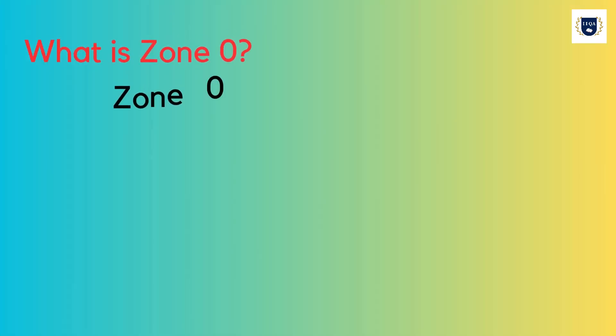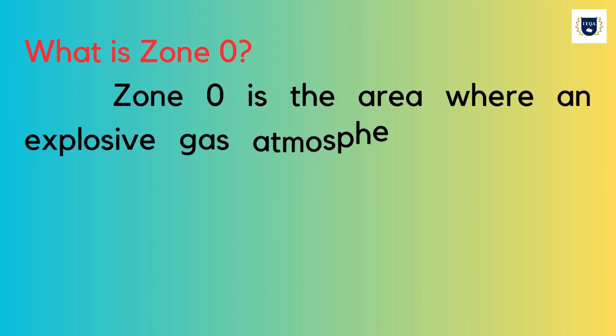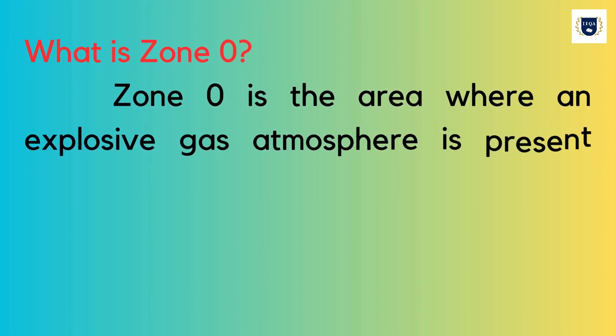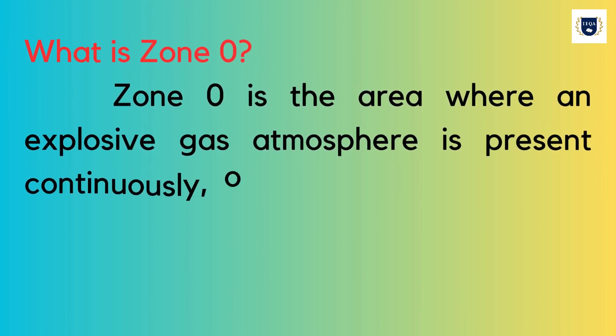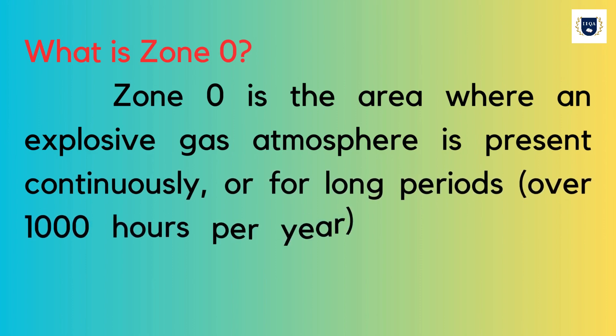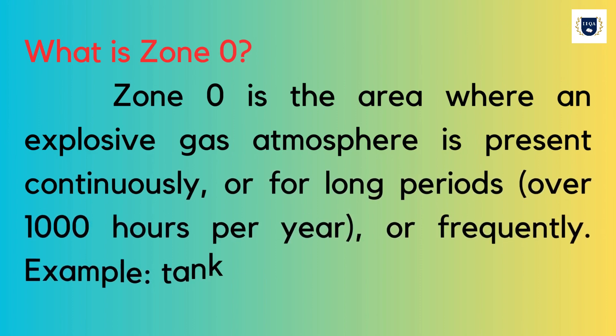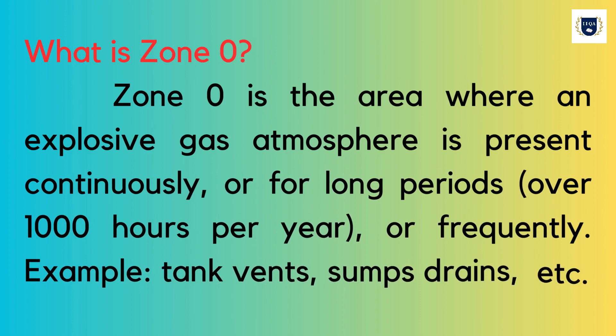What is Zone 0? Zone 0 is the area where an explosive gas atmosphere is present continuously or for long periods — over 1000 hours per year — or frequently. Examples include tank vents, sump vents, drains, etc.